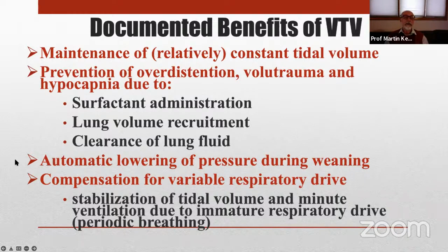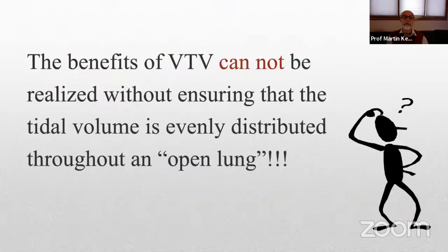Equally important is the fact that the ventilator lowers or adjusts inflation pressure in real time. It doesn't wait for the next blood gas. It doesn't wait for morning rounds. It doesn't worry that the professor will chastise it for making the wrong decision. It does what it's programmed to do and leads to more rapid weaning from mechanical ventilation. And finally, it also compensates for the highly variable respiratory drive of an immature infant who has a lot of periodic breathing and brief periods of apnea. And volume targeted ventilation will make that adjustment in real time. So that's one half of the equation.